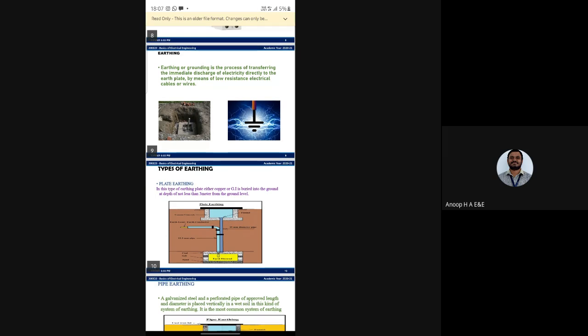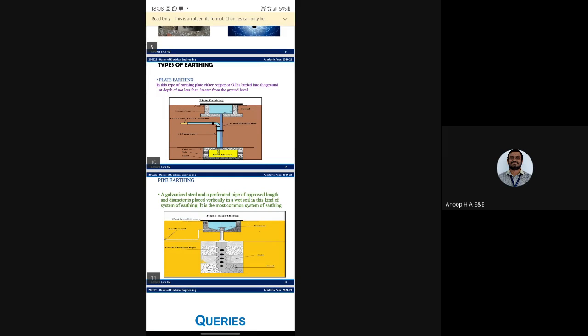Earthing. Earthing is important because if we get a shock, earthing in our home keeps us safe. Earthing or grounding is a process of transferring immediate discharge of electricity directly to the earth by means of low resistance electrical cables or wire. Types of earthing. Plate earthing. This is a type of earthing using a plate, either copper or galvanized iron.